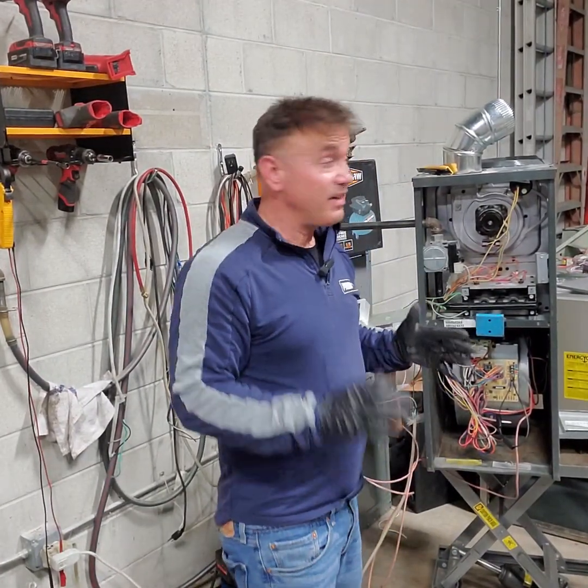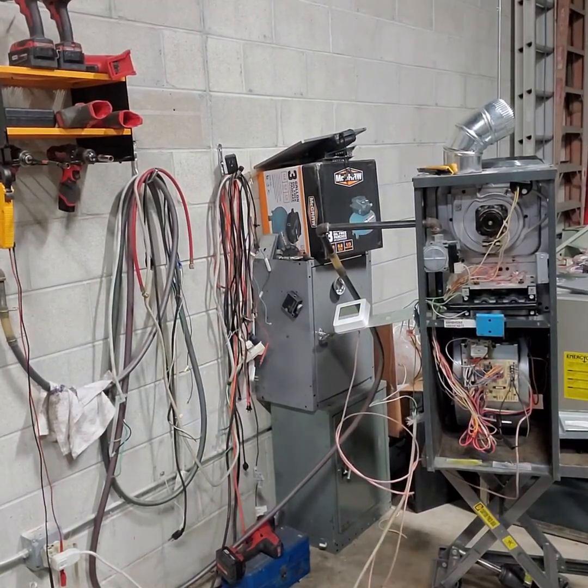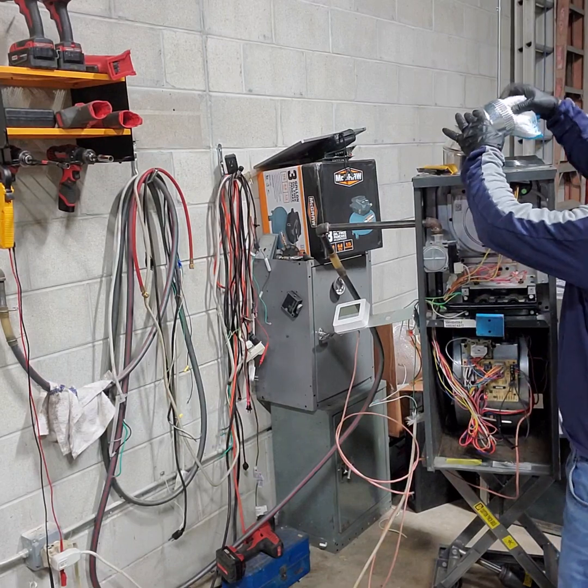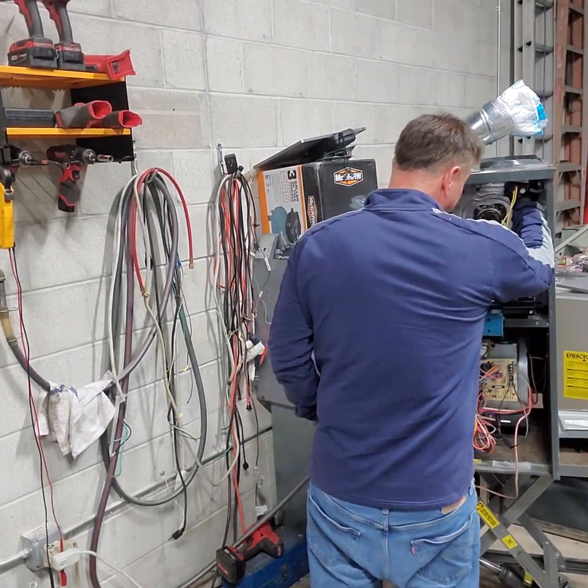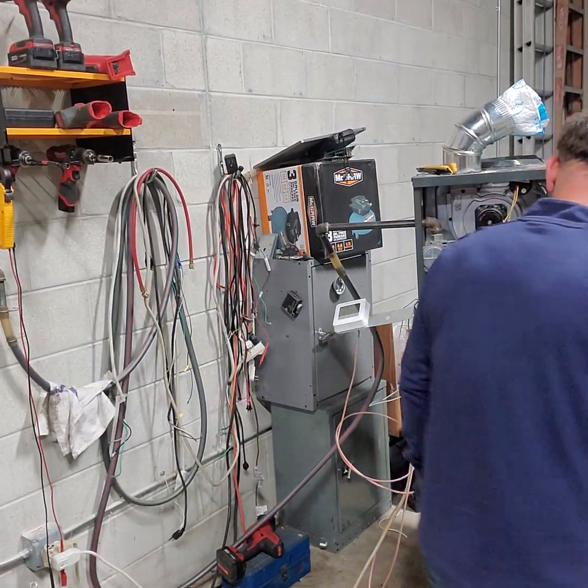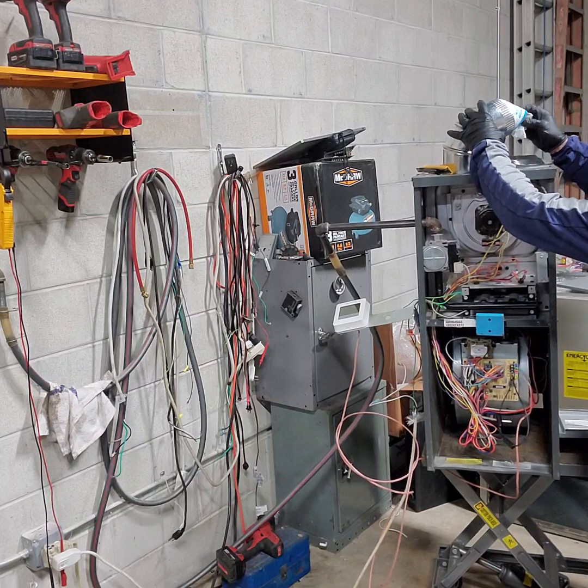The dangerous thing could be in the chimney. Like for example, I'll show you now. I'm gonna simulate like there's something inside blocking the chimney, right? I'm gonna simulate that. I'm gonna put this here, and then I'm gonna put this here. Even if I connected it now, most likely, wow, it connected. I'm gonna block it worse than that, because usually that's how the restriction happens.